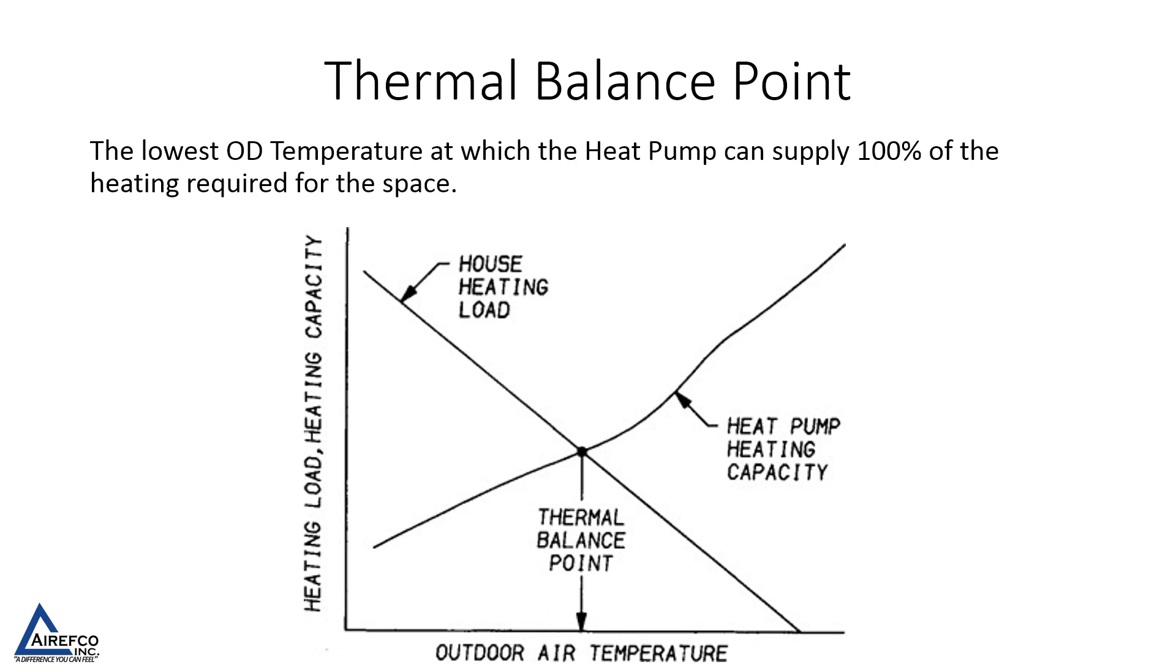This is the lowest outdoor temperature at which the heat pump can supply 100% of the heating required for the space. Where the heat load line and the capacity line of the heat pump intersect is the thermal balance point for that particular unit.